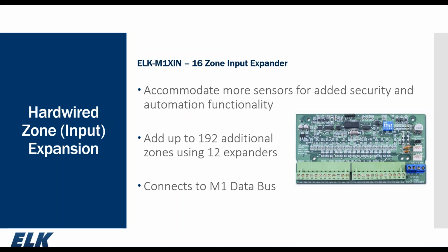Beyond the 16 onboard zones, we have our M1XIN. This is our hardwired 16-zone input expander. You can have up to 12 of these connected to the data bus, which will give you an additional 192 zones. They can be located at the panel or they can be remotely located. They are part of the data bus, so that gives you the versatility of being able to remotely locate the input expander and then hardwire your sensors to it and so forth.